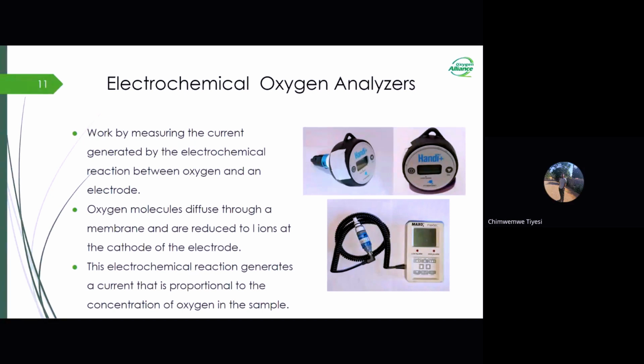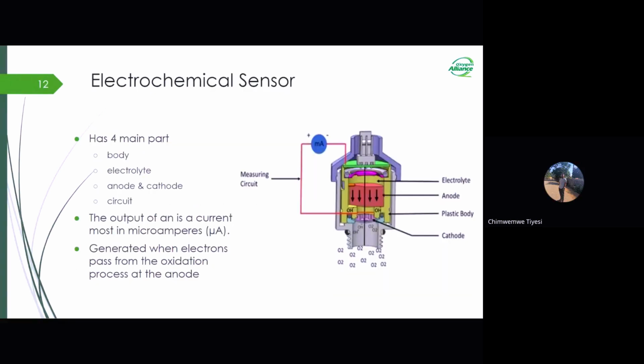Most of these electrochemical oxygen analyzers have replaceable electrochemical sensors in them. Next we'll look at these electrochemical sensors, how they are built inside, and I'll show you a closed section area of this oxygen analyzer. So moving on. As you can see to your right in the graphics, there is the electrochemical oxygen analyzer. It has 5 main parts.